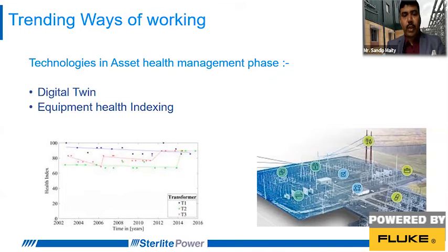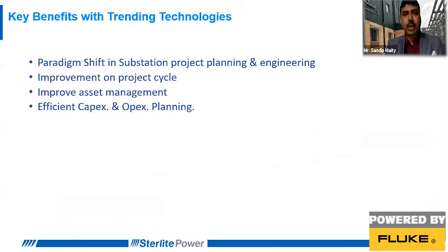Even if you have 20 transformers, 30 breakers, 50 isolators, 30 CTs, whatever your components are, maybe digital sets, you can put all that equipment data into your software based on field data received so far, and then index your equipment to predict its health. Should you take maintenance now, or delay it since it can run fine for another 6 months or a year? That's how this technology helps you make decisions.